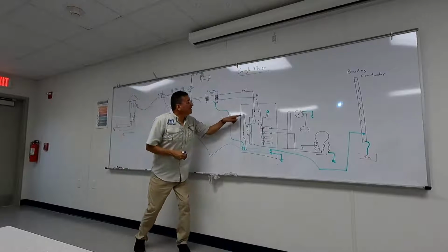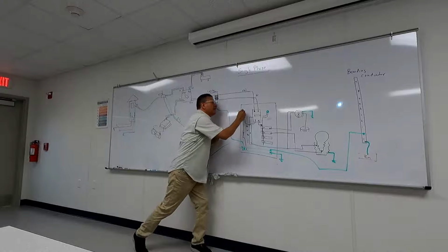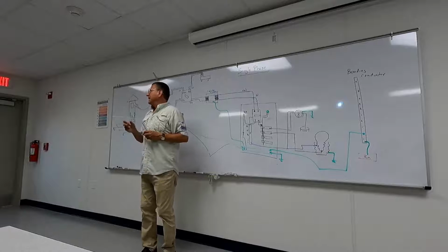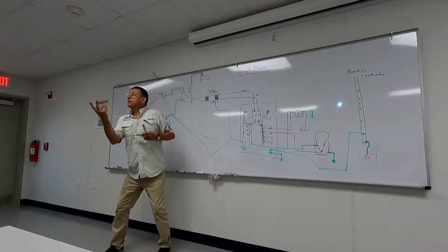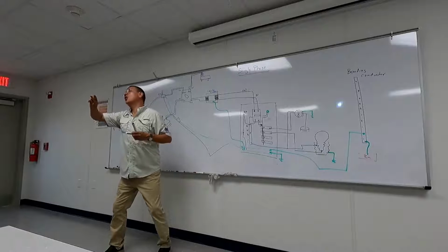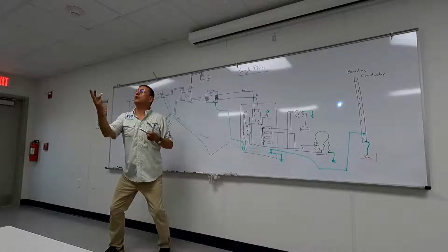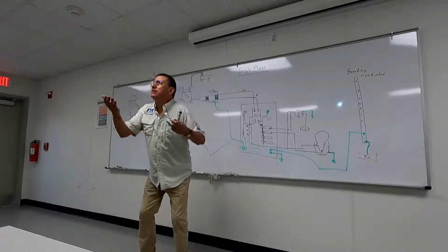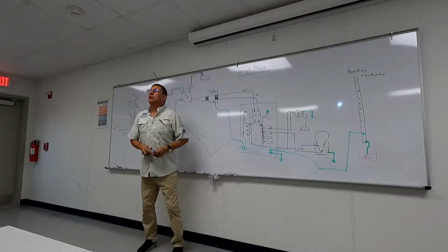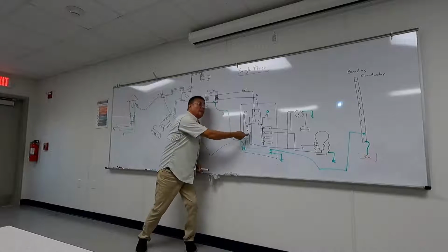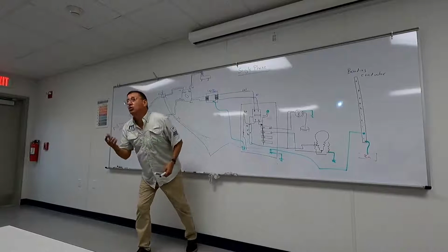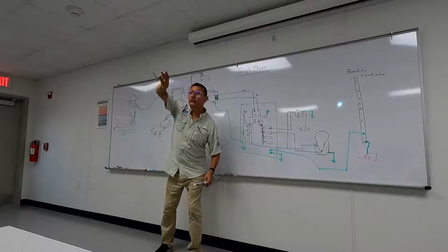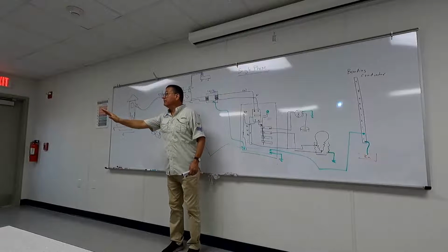What is the function of the reverse polarity indicator? It indicates if the neutral bus bar is powered and the hot bus bar is neutral, a switch between both phases. Where is the reverse polarity indicator connected? One leg on the neutral bus bar and the other leg on ground, to indicate if hot and neutral are switched.